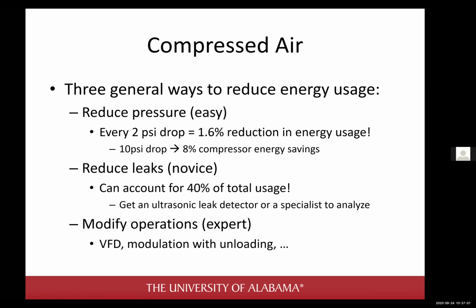You may need an ultrasonic leak detector, or you might need a specialist to come in and analyze your leaks. There are ways to put a number on the amount of leaks that you have through monitoring power input to your compressors. And that's something we do at the Industrial Assessment Center. Every assessment we go on to a manufacturing facility, we put these little current transducers on the 3-phase power. One of the leads of the 3-phase power going into the air compressor, we put a current transducer on there and we monitor power usage. Well, we monitor amperage, which is a surrogate for power usage, but we monitor it for a week and we figure out how loaded your compressor is and how much air it's making.